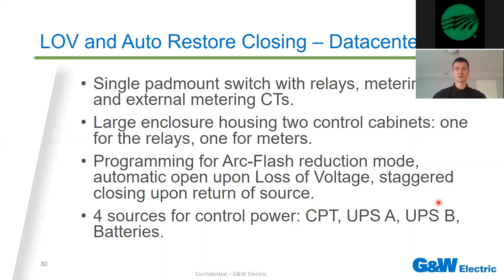What we provided here is programming for arc flash reduction mode and an automatic open upon loss of voltage, with a staggered closing upon return of the source. So if the utility feed is lost, we see an automatic open, and then a bunch of UPSs, backups, and generators take over. But as soon as the utility voltage comes back, each and every way on the switch, with the associated loads, is closed in a staggered manner to avoid a high inrush current and bring the big loads on gradually.